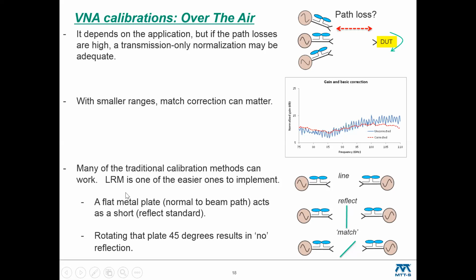And an important point about this algorithm family is you don't really need to know much about this reflect standard. It's not like short open load where you have to tell it the S parameters. It really just requires that the reflect be symmetric. So you can be a little bit sloppy with this standard and not take a big uncertainty hit. And the match, while you could put an absorber in here to take care of it, actually, if you're in a chamber and the walls are reasonably absorptive, if you just tilt this plate at a 45-degree angle, you're really getting no reflection into the antenna. And that works reasonably well as a match standard.